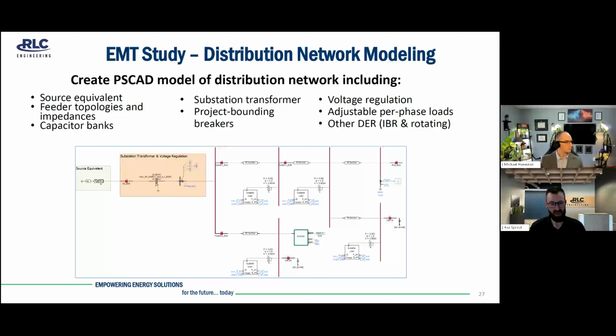Voltage regulation, such as transformer LTCs, bus regulation, and line regulators. Adjustable per phase loads. So we do unbalanced load modeling here per the provided distribution network model for accuracy's sake. And then any other DER that's located with the model. So if it's IBR, then it's typically going to have a PSCAD manufacturer model provided.